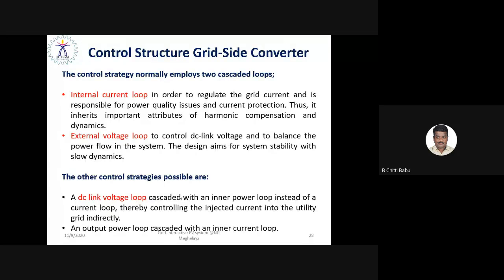Yes, now the control structure. As I told you, the grid side converter is the component that satisfies the grid integration, or grid connection requirements. It has a cascaded control loop, basically an internal current control loop and an outer voltage loop. The internal current control loop regulates the grid current or inverter output current, because the inverter has to be protected against any overcurrent. The inverter is designed to carry the rated current of the grid. If the grid current exceeds the rated current, the inverter is going to be overloaded, and hence the switches may be damaged at any cost. So in order to protect the inverter switches against overcurrent, the current regulation is very essential, and that has been incorporated with the internal current control.